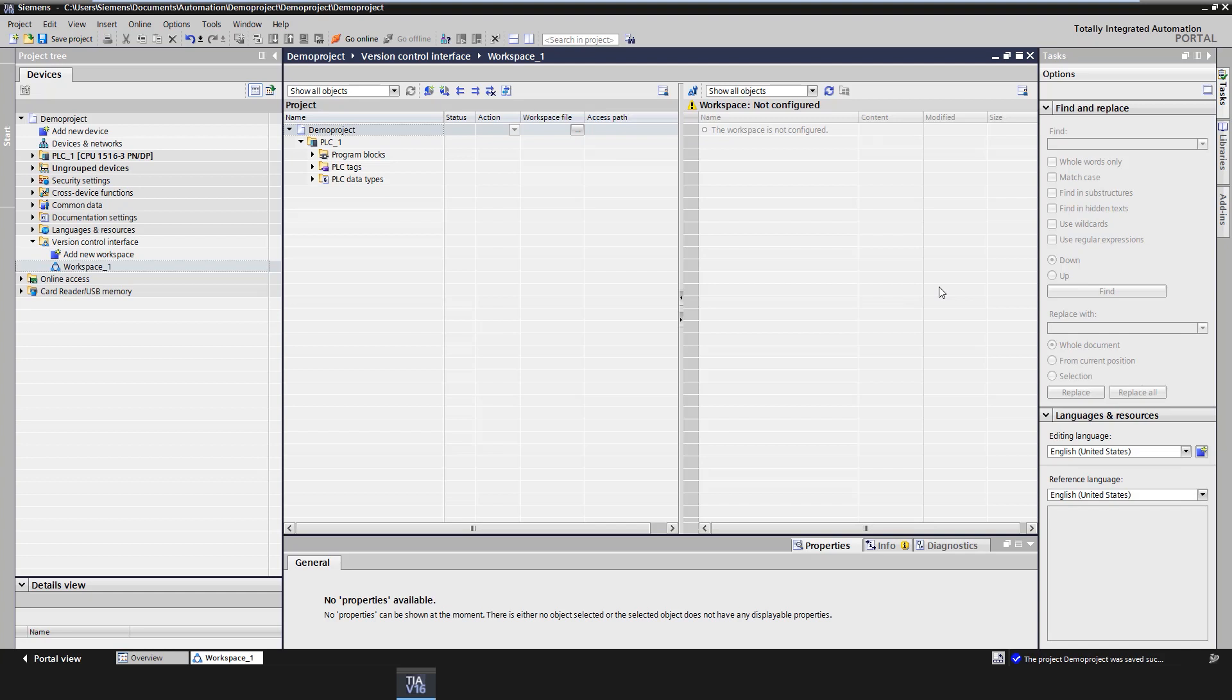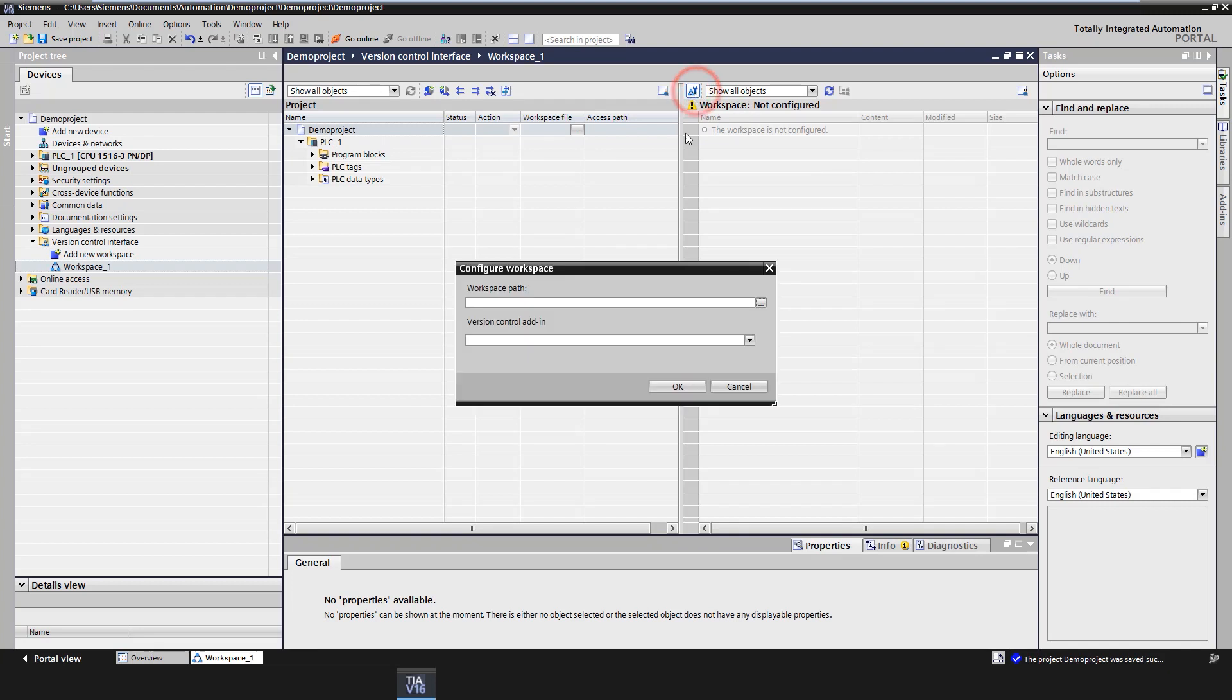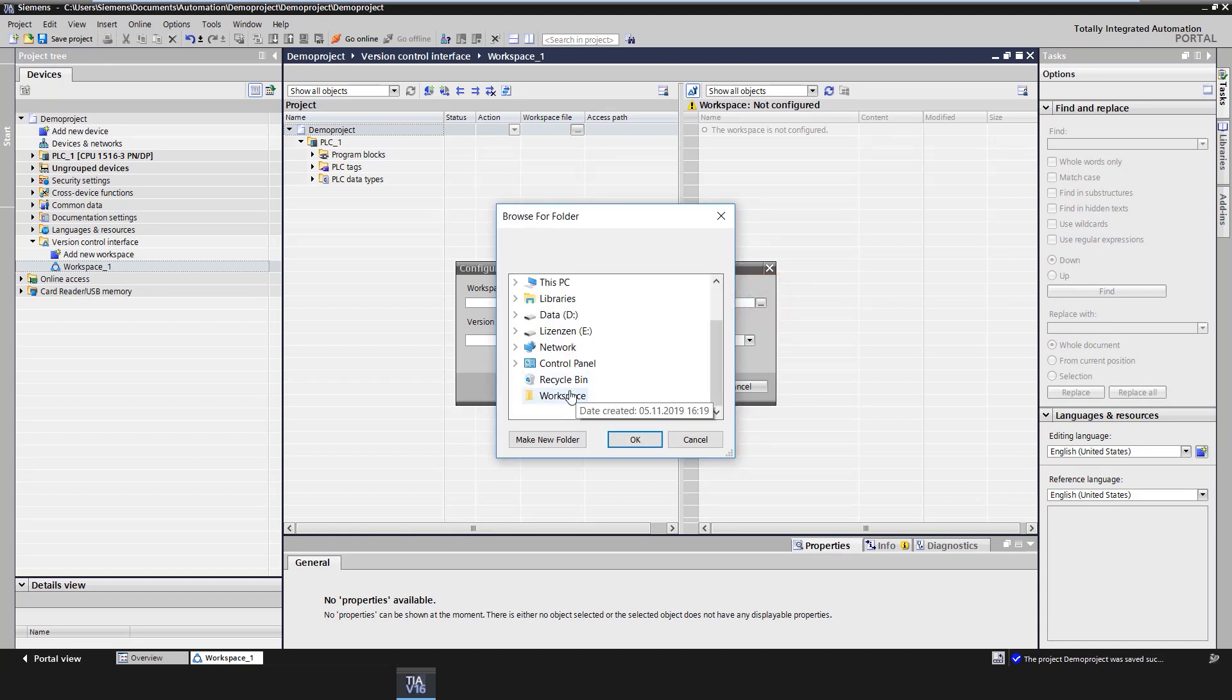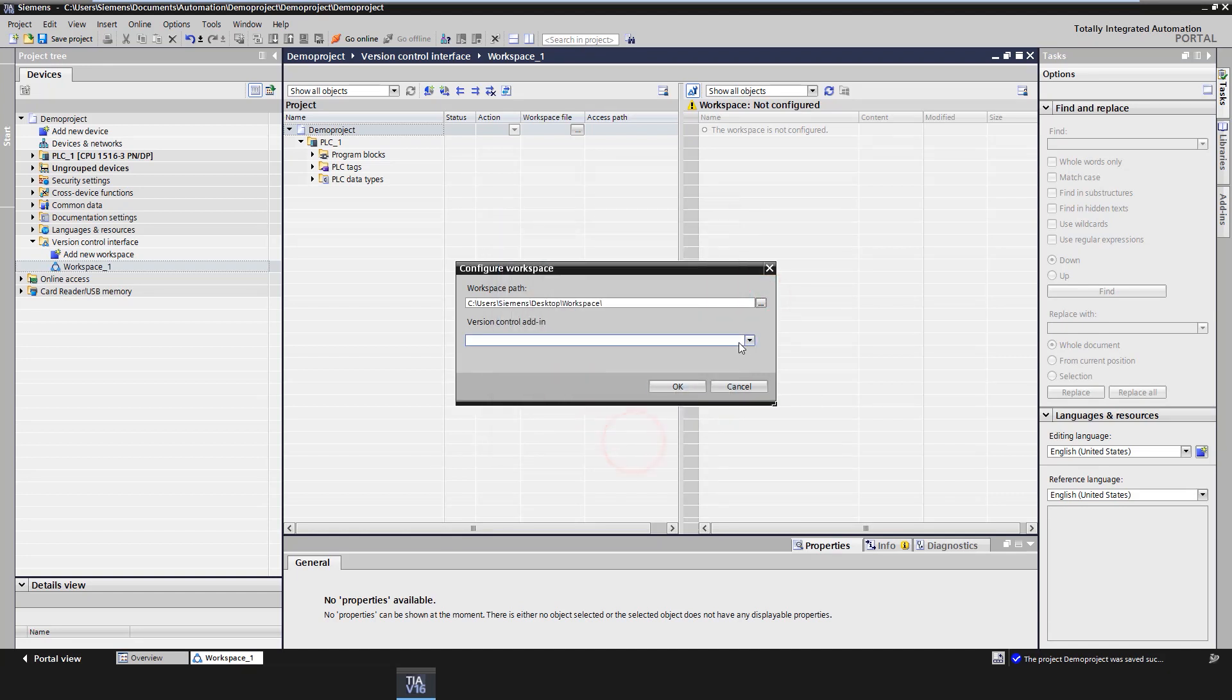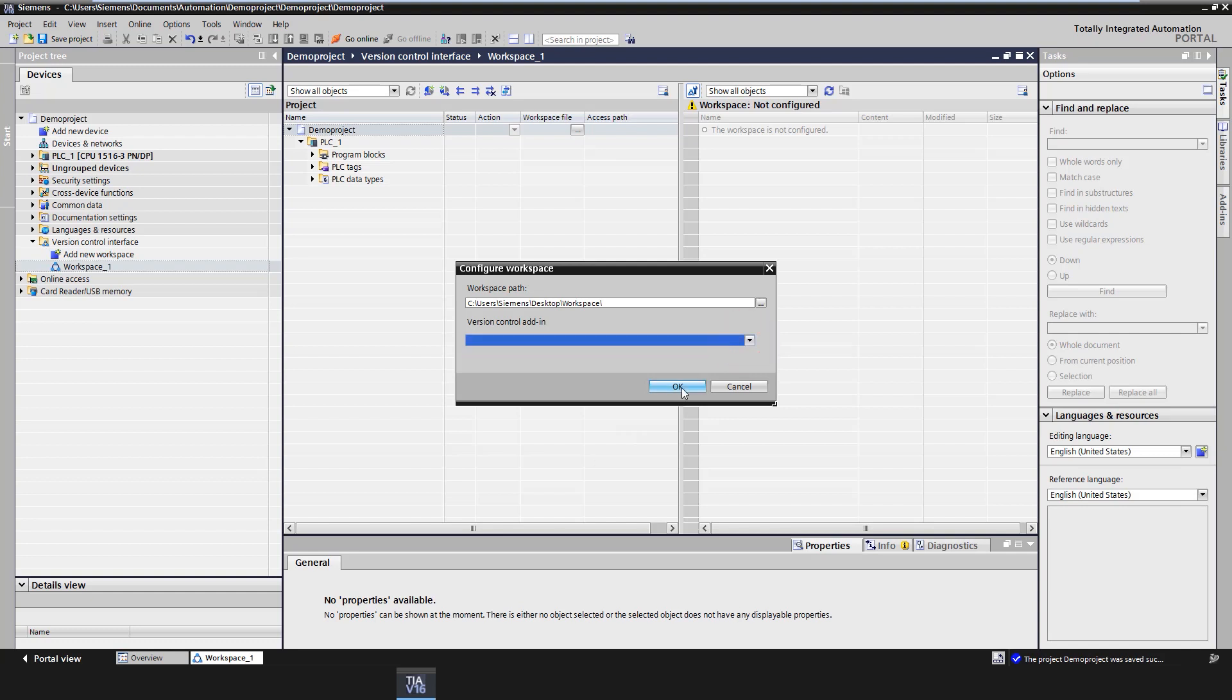Once the VCI workspace has been created, it must first be configured and linked to a Windows directory into which the elements to be versioned are then exported. First, click on the Configure Workspace button and a configuration window will open. In this window, the file path to the Windows workspace must be specified. Furthermore, there is the possibility to select an add-in for the connection of the workspace to Git or other versioning systems, if such a TIA Portal add-in is available.